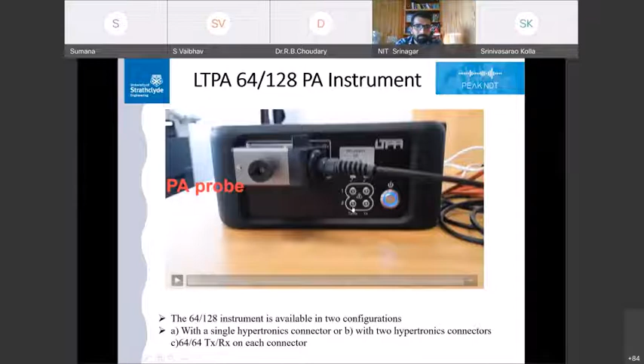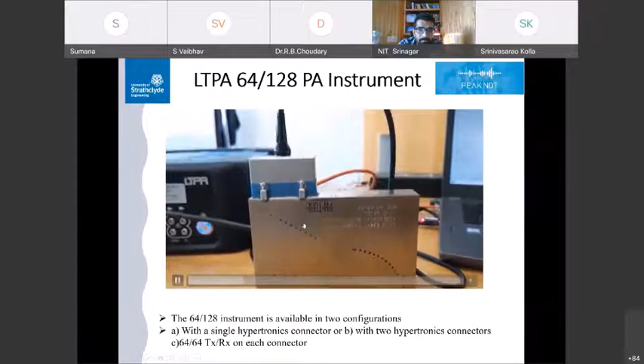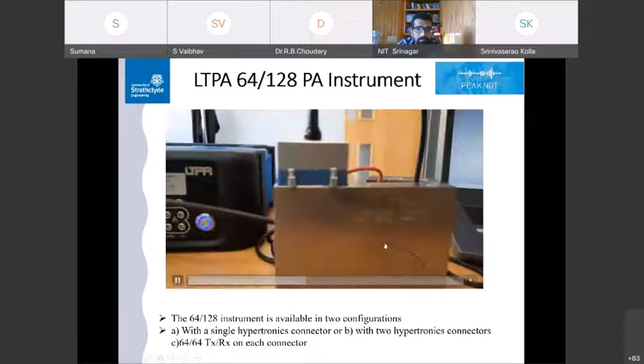So these are the conventional channels, and this is the phased array probe, which is connected here. And now I am inspecting this area. So these are all the side-drilled holes situated in a diagonal manner. And I'm just connecting the USB cable from the instrument to the laptop. This is the front panel, where the B scan image shows all the defect signals with very high sensitivity, and this is the A scan signal. So these are the signals we acquired.